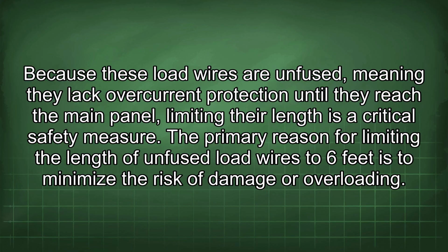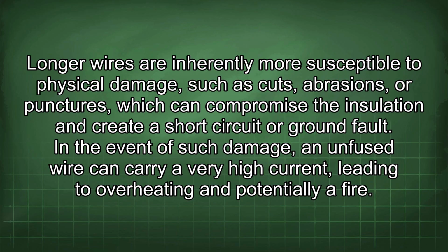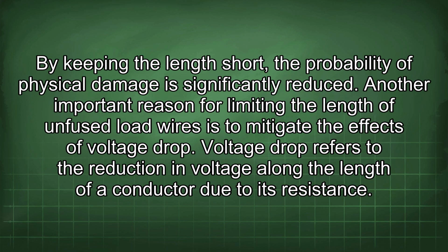The primary reason for limiting the length of unfused load wires to 6 feet is to minimize the risk of damage or overloading. Longer wires are inherently more susceptible to physical damage, such as cuts, abrasions, or punctures, which can compromise the insulation and create a short circuit or ground fault. In the event of such damage, an unfused wire can carry a very high current, leading to overheating and potentially a fire. By keeping the length short, the probability of physical damage is significantly reduced.